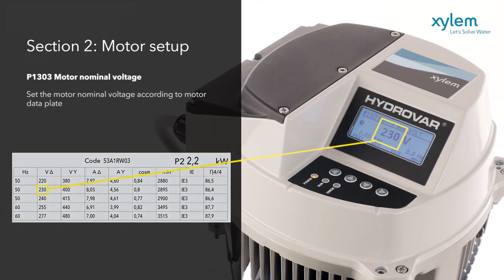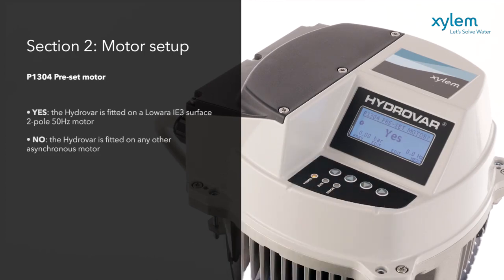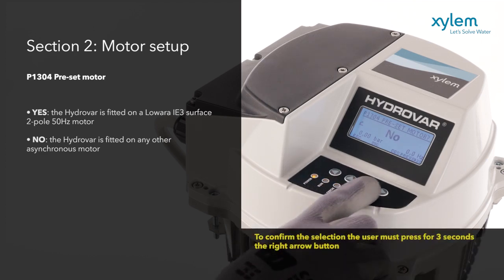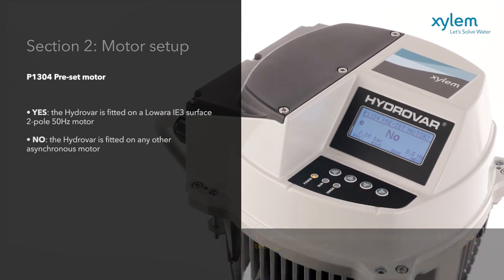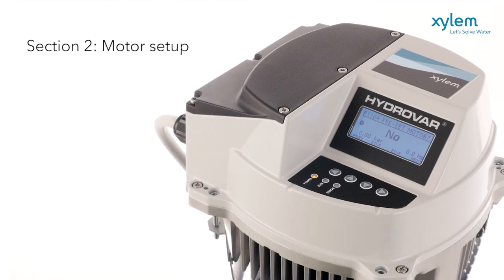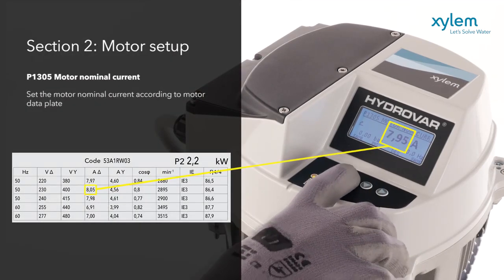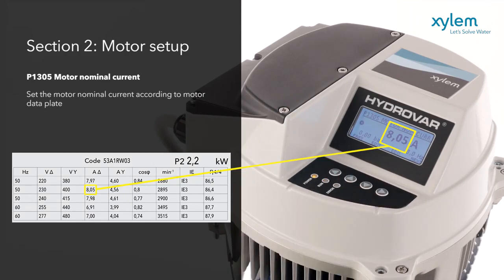Or you can just select the data for a Lowara IE3 2 poles 50 Hz motor, which is already built into the software, or simply select a generic motor. If No is set, additional steps are required to let the Hydrovar identify the correct motor parameters. Otherwise, go directly to the STC thermal protection settings. If a generic motor is selected, the nominal current and nominal speed of the motor has to be set.